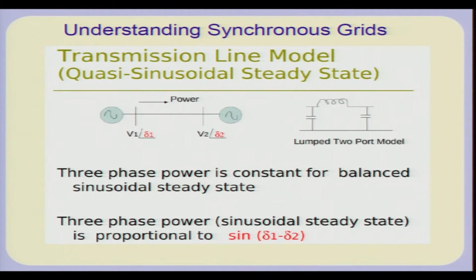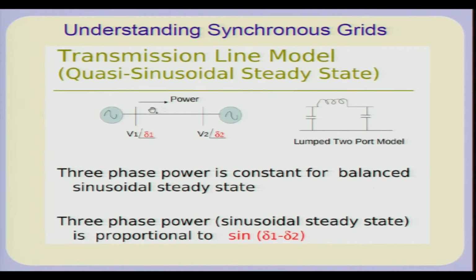Now, one of the points to keep in mind is that this power flow is not proportional to delta 1 minus delta 2, it is proportional to sine of delta 1 minus delta 2, and that is not a linear function. So, it is not that if I increase delta 1 minus delta 2, power flow will proportionately increase; it will increase in proportion to sine of delta 1 minus delta 2. And of course, the power flow is dependent on the reactance x. For the simple lossless system, it will be V1 V2 sine(delta 1 minus delta 2) divided by x. But this variation is non-linear with respect to delta 1 minus delta 2, that is one important point.